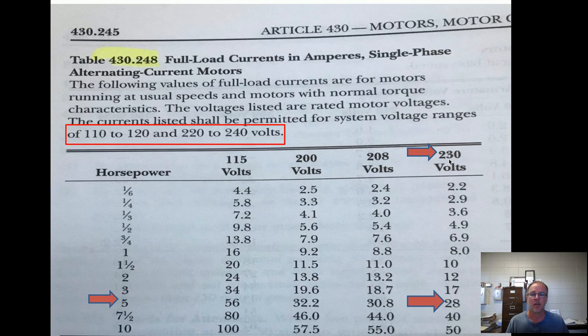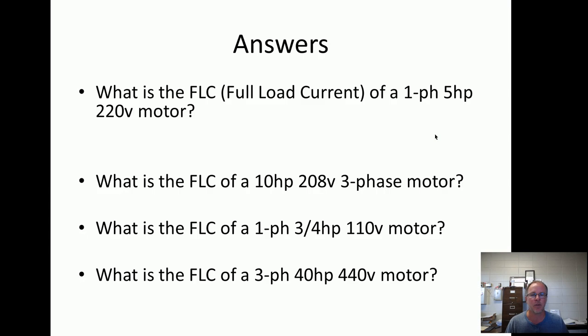Same thing with 115 volts — if the question calls for a 110-volt five-horsepower motor, you're going to use the 115-volt chart. That's kind of a trick question they throw at you sometimes on the Journeyman prep.